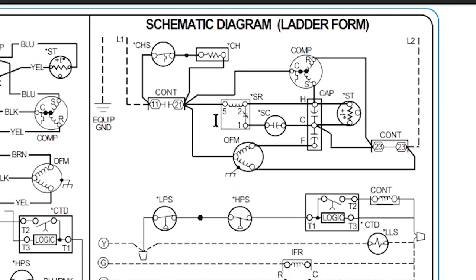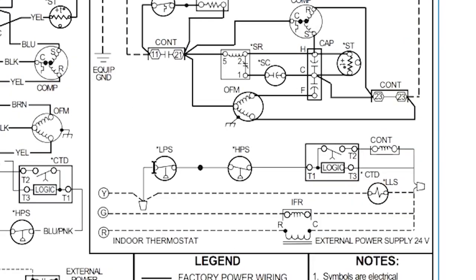The outdoor fan motor: we feed the common terminal on the outdoor fan motor with one side. This diagram doesn't show a thermal overload for the outdoor fan motor, but it does have one — it's just not shown. We've got the common terminal, the fan winding going to the capacitor, and the run winding connecting to L2. The fan connects to one side of the solid bar on the contactor, and the compressor to the other side — on a single-pole contactor both sides are exactly the same.